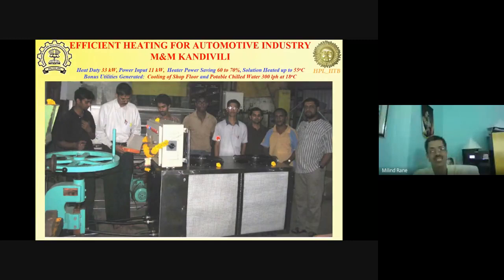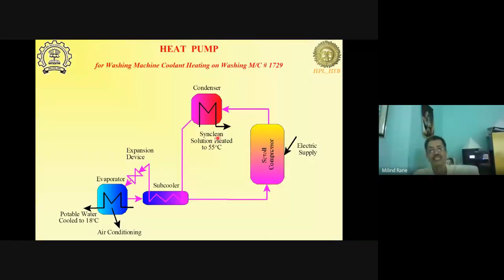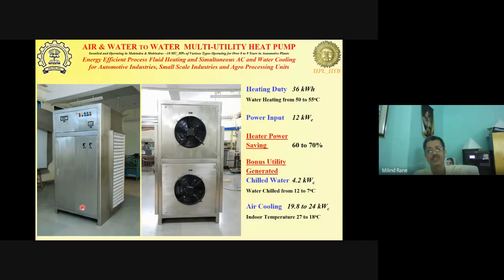This was the team at the time. So this is how the unit gets integrated. The condenser is used to heat up the solution. The tube heat exchanger is deployed here to directly integrate in a very reliable manner, heating the solution up to 55. And then on the evaporator side, air conditioning is the primary utility, and as and when chilled water is needed, you can chill the water also. So this unit I already discussed at the time, and it can be used for generating multiple utilities. It can be used for simultaneous heating and cooling of fluids. It can be used in automotive industries, small scale industries, agro processing units, and so on. And now we are deploying it in hotels and other things also, and residences also, very small units of 1.5 ton systems for that.